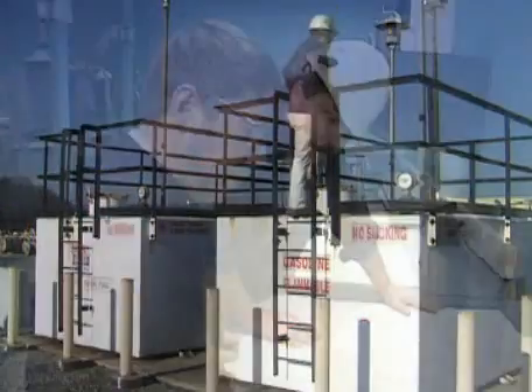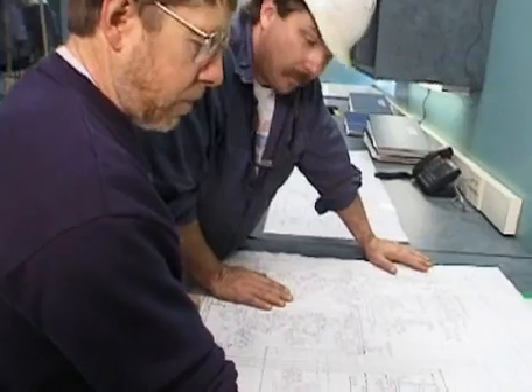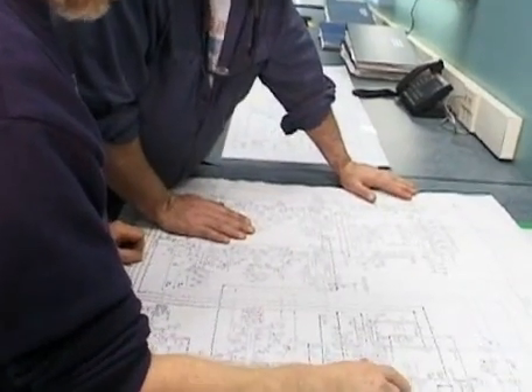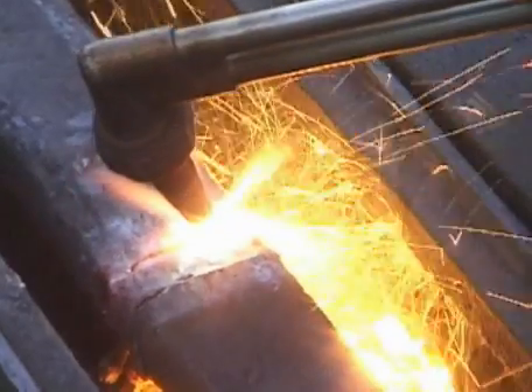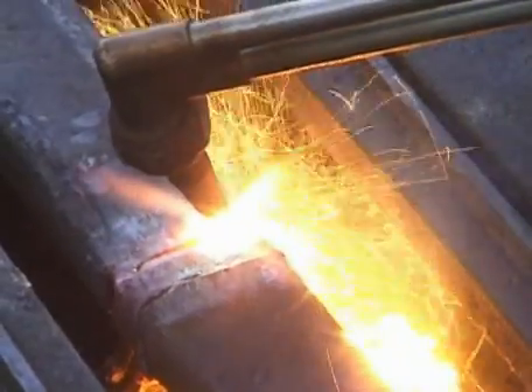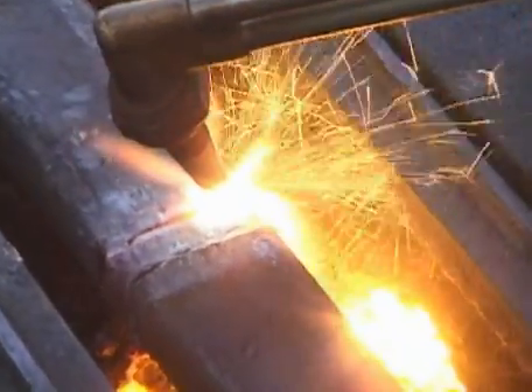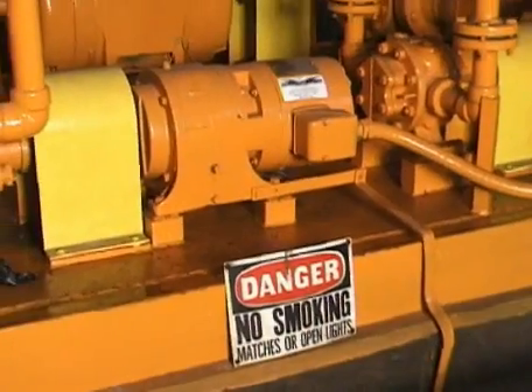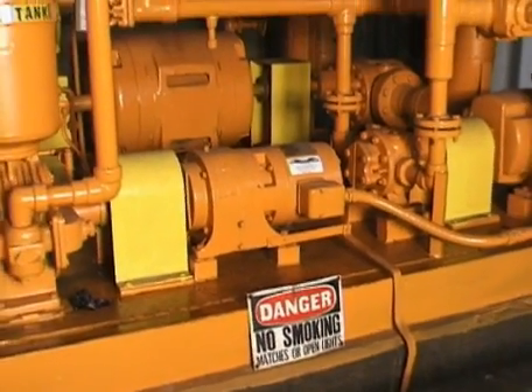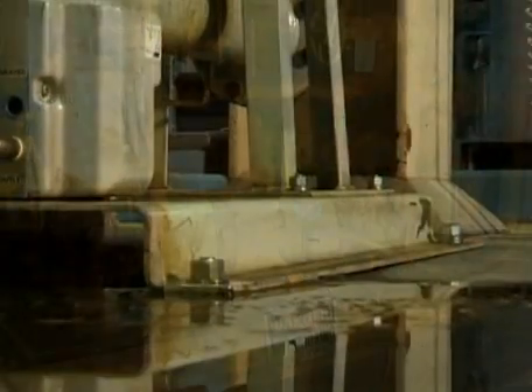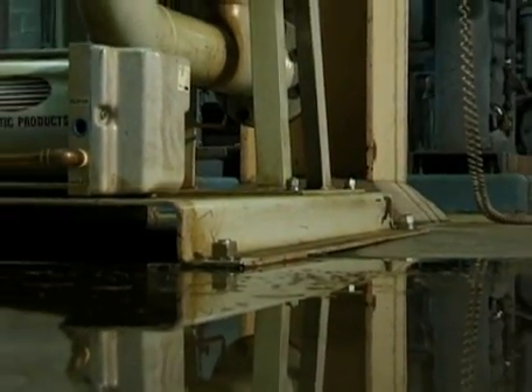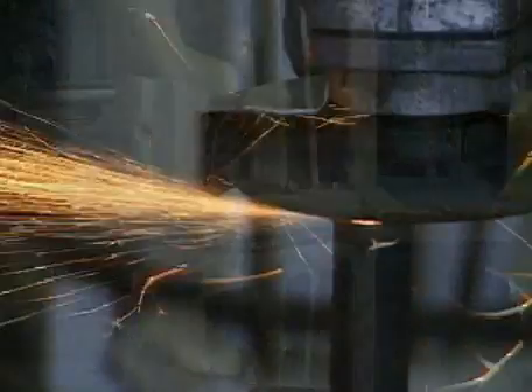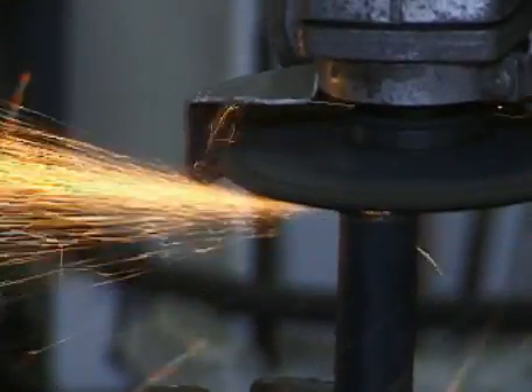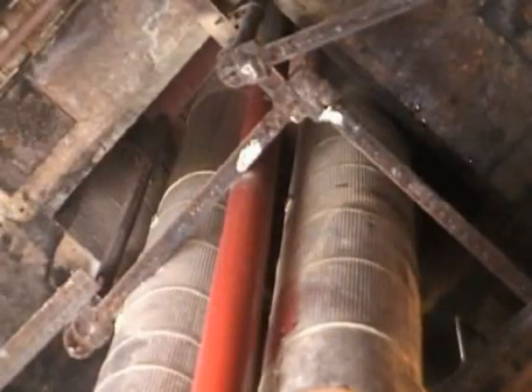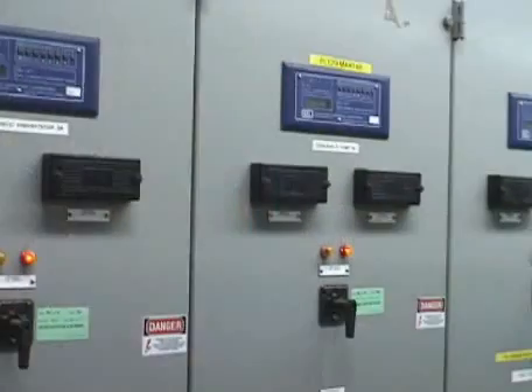Before work is initiated in any plant system with a high fire risk potential, PPL's hot work permit must be utilized. The objective of the hot work permit is to prevent fires from occurring by preventing ignition sources from reaching combustible or flammable materials that are stored or released, and by preventing released combustible and/or flammable materials from reaching ignition sources, including open flames, sparks, high-temperature steam piping, and electrical sources.